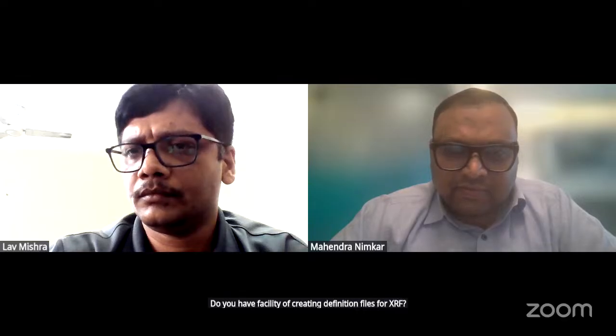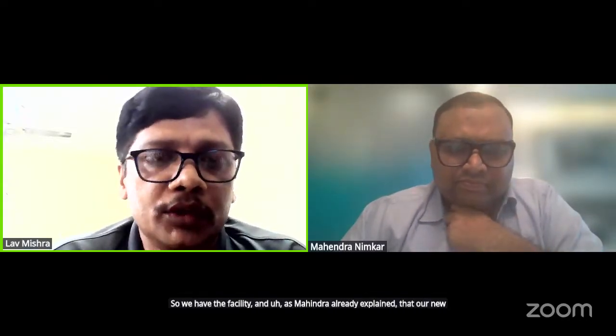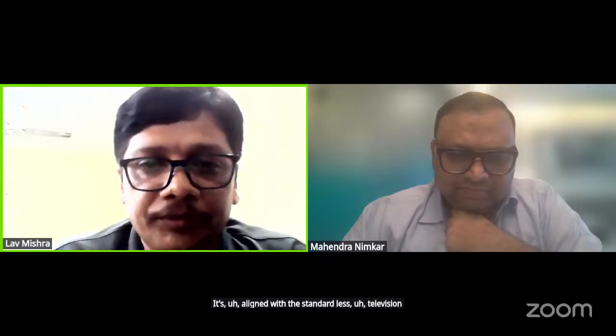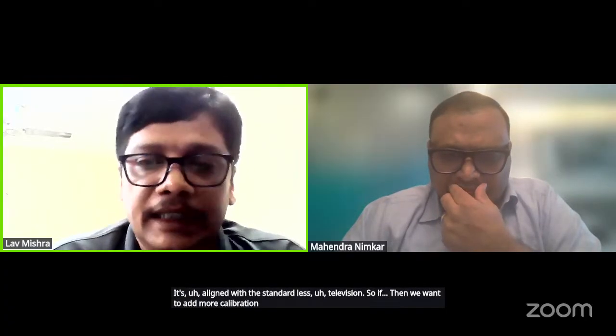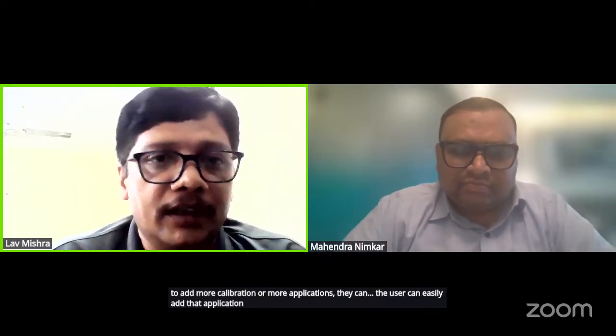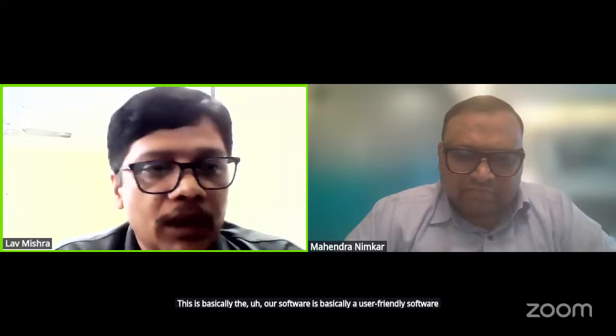Do you have a facility for creating definition files for XRF? Definition file, I correlate that with the application, right? Calibration files, correct. So we have the facility, and as Mahindra already explained, our new instrument, the FT230 model, is aligned with standard-less calibration. If users want to add more calibration or applications, they can easily add them even without a standard. Our software is user friendly. With just one training, you can add the standard as well as the calibration and application.